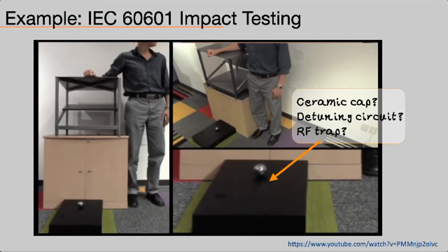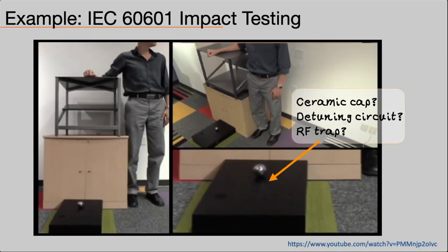So this is one of the tests - you have to drop a half kilogram ball on every point of your coil. So imagine what would happen to a ceramic capacitor, a detuning circuit, PIN diode, or RF trap under this test. Now, while the device does not need to work after this test - that is not a requirement...